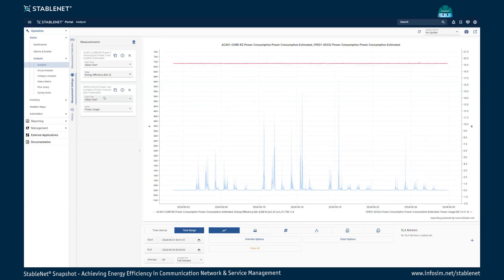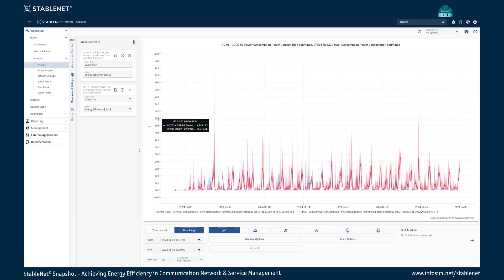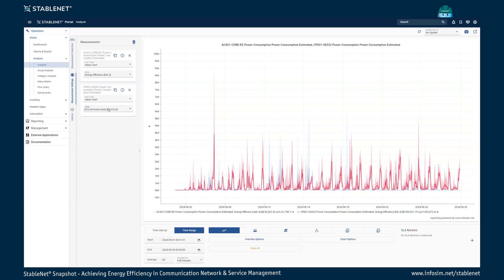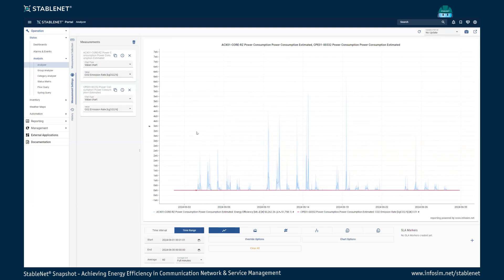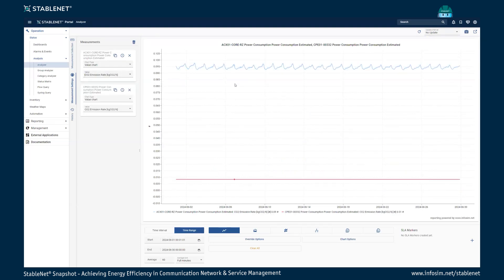The power consumption is not strongly dependent on the actual bandwidth going through the network device. Therefore we also have additional measures, such as energy efficiency, which shows how efficient the system is — basically a number for comparison between two devices. We also have CO2 emission rates, which correspond one-to-one to the actual power consumption, calculated as power multiplied by some carbon intensity based on the energy mix used.